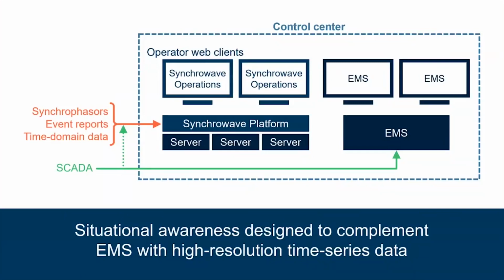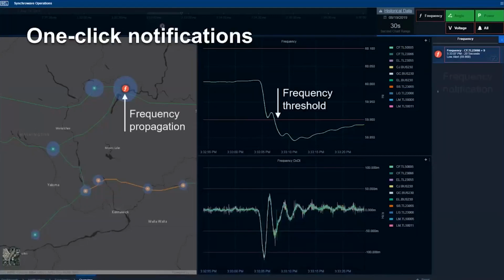So let's look at how this software looks, or what information this software provides. Next I'm going to show you a few screen captures from the software itself. Whenever you have any power system conditions or power system anomalies, it gives you a one-click notification. When you click on this notification, you get all the information. So this is the notification that I'm talking about. When you click on it, you get the source of where this notification started, and you also get what happened. You can see that this was my frequency threshold. My frequency went below the threshold, and that's why I got a notification.